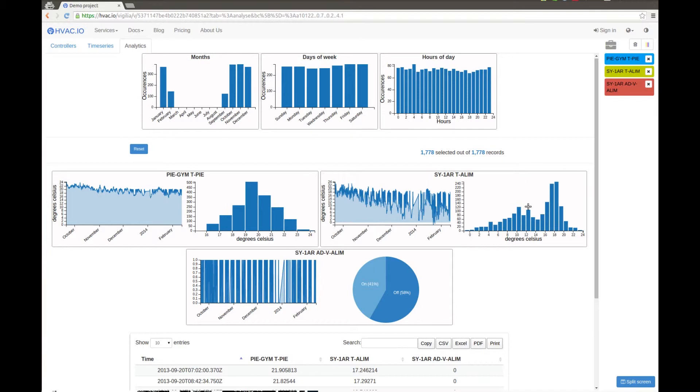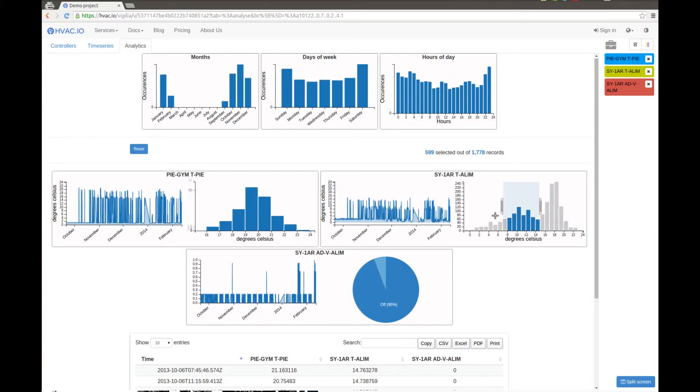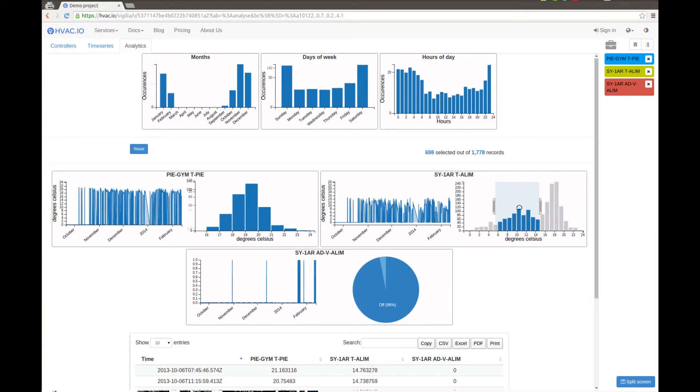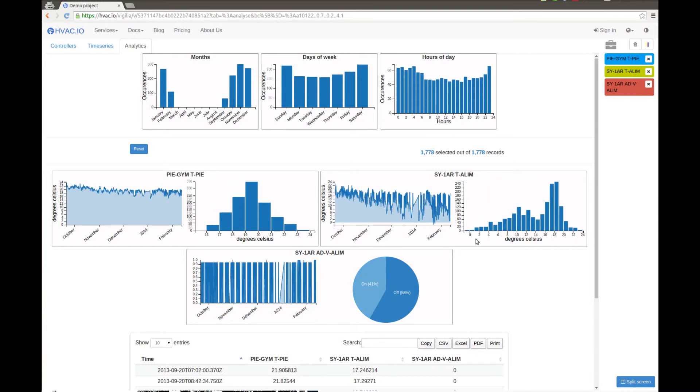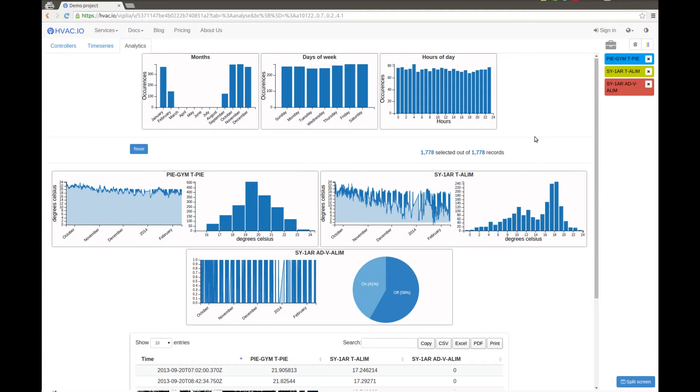So to understand what's happening, we will check for the lowest temperature curve. Oh, look, it's when the fan is not working. So we recorded data probably at night when the fan was not working and there was some cold air infiltration.